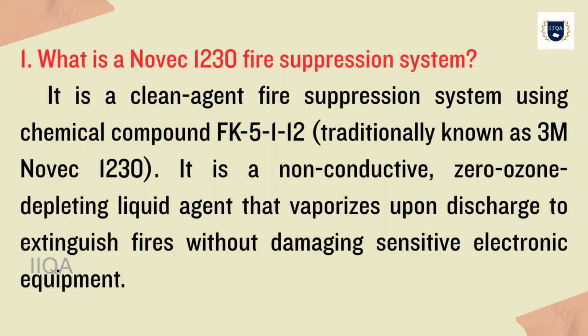1. What is a Novec 1230 fire suppression system? It is a clean-agent fire suppression system using the chemical compound FK-5-1-12, traditionally known as 3M Novec 1230. It is a non-conductive, zero-ozone-depleting liquid agent that vaporizes upon discharge to extinguish fires without damaging sensitive electronic equipment.